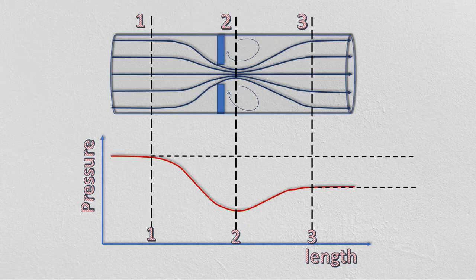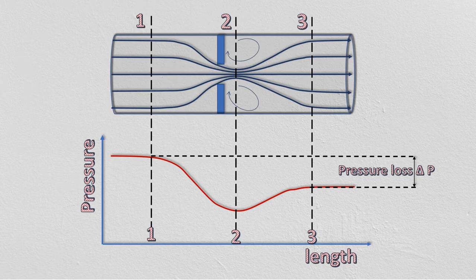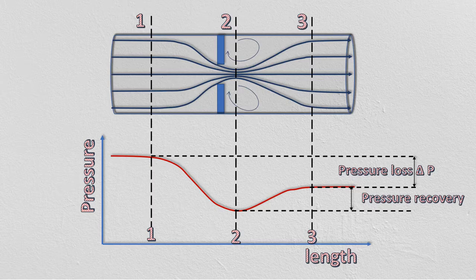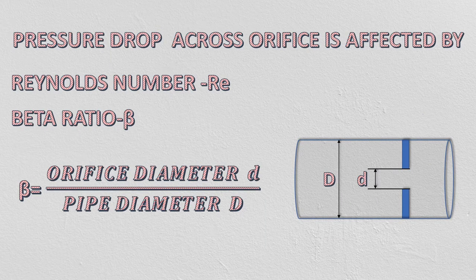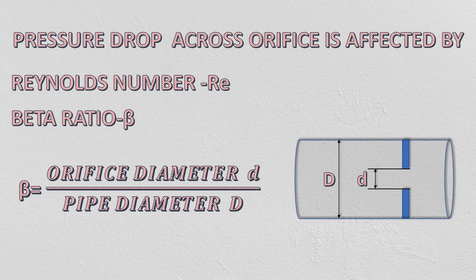The pressure difference between sections 1 and 3 is non-recoverable and known as permanent pressure loss. The pressure difference between section 2 at vena contracta and section 3 is known as pressure recovery. Pressure drop across orifice is mainly affected by Reynolds number and beta ratio.